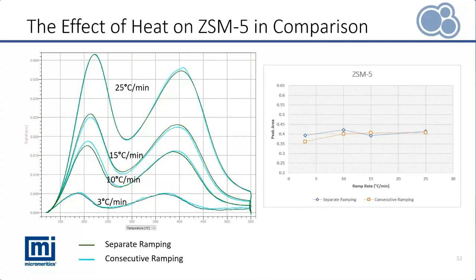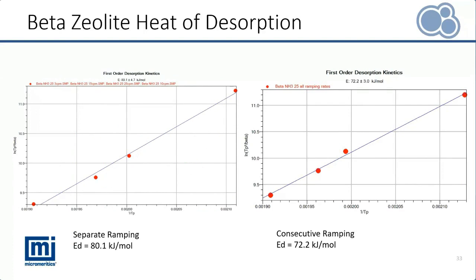Here are the first order kinetics plots of the weak acid sites in beta zeolite from the separate ramping experiment on the left and the consecutive ramping experiment on the right. We see different heat of desorption values resulting from the different experimental approaches. So if we are aware of a material susceptible to heat, then separate ramping should be employed by preparing a fresh sample for each TPD analysis to accurately characterize acidity and the binding strength of the material. The AutoChem 3 allows heat of desorption calculation from several different sample files to successfully calculate a more accurate heat of desorption of an acid site.